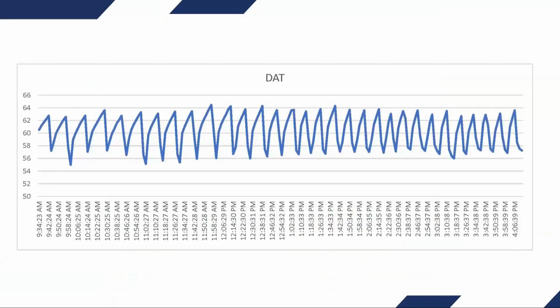This is a sample of one of the trends that we took. This particular trend, we were taking readings about every 8 minutes. We will adjust that time depending on what the trends look like. 8 to 10 minutes is usually a good starting point. You can see the lowest temperature that we typically would reach was about 56. The highest temperature was about 64, averaging about 60-degree discharge air on these fan coil units. And we know from the previous slide that we need at least 56 degrees before we can remove any moisture from that building.